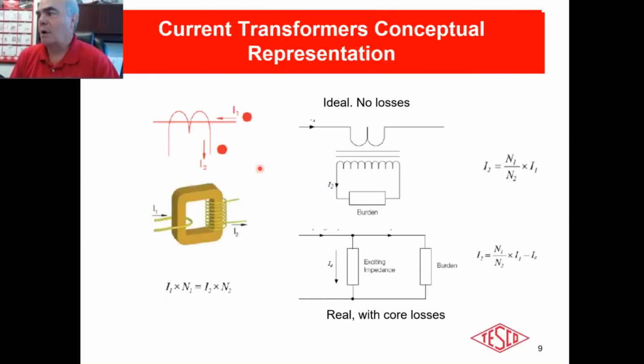How does a CT work? It's pretty basic. All right. The number of windings, that's your ratio. So if I've got a 400 to 5, that's a ratio of 80 to 1. That means I got one primary and I got 80 of these secondaries. All right. And it's a direct correlation between current 1 and current 2. In a perfect world, there are no losses. Okay. So I2, the secondary current, is equal to I1 times the ratio of the coils, 1 to 80 in this case. Okay. That would give us a 400 to 5 CT.